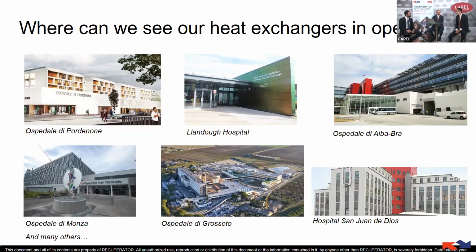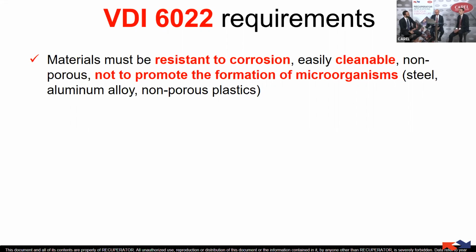why a proper humidification system is important to maintain a good hygienic level inside the air handling unit. Yeah, for sure, humidification is one of the most important parameters that we have to guarantee inside the confined space for a critical application like hospitals, but not only for critical applications, also for commercial ones. Yeah, as the first poll confirmed as well. So in order to design and define the right requirements for humidification, we have to come back to the norms and regulations that give all the details to refer to, in order to choose the right humidifier for hygienic and safety applications. VDI norms give requirements in terms of material, because our humidifiers, and CAREL is a leader in the production of humidifiers, are devices and equipment built with this characteristic.